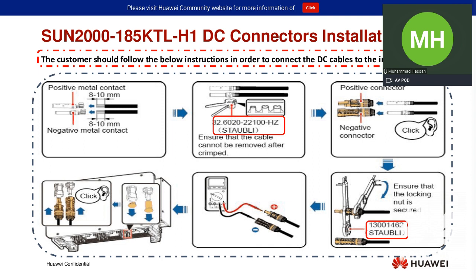Installation of DC connectors. Yes, as you can see in the picture, you need to strip off the DC cable from 8 to 10 mm, and you need to test the polarities first, as I mentioned before. Then strip off the cables, then connect the correct metal pin, the positive metal pin with the positive cable and the negative metal pin with the negative cable, which come inside that inverter box, and crimp that pin properly with the proper crimping tool, so that you will not face any problem in the future. Here again, you need to use the Staubli tool with the die number 60202210. This is very important, that you use the correct die for crimping the pins of the DC connectors.